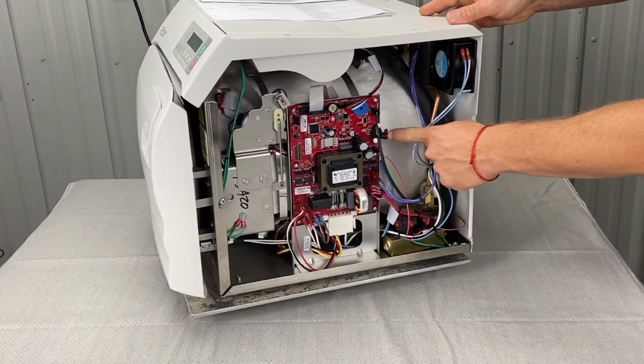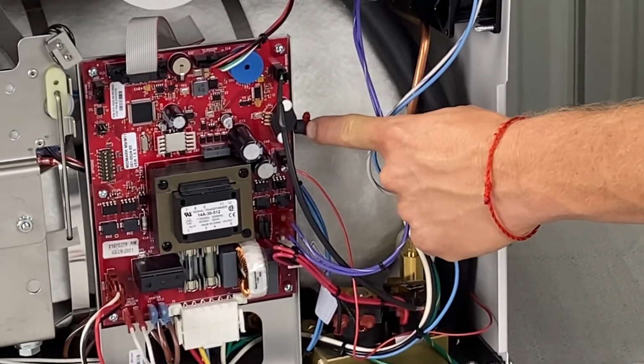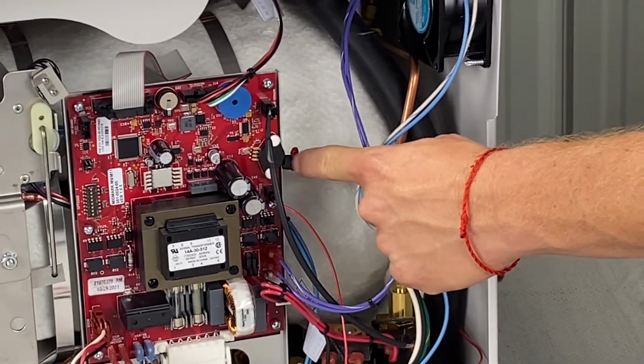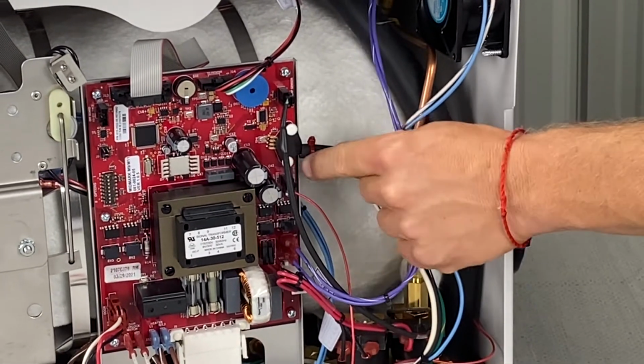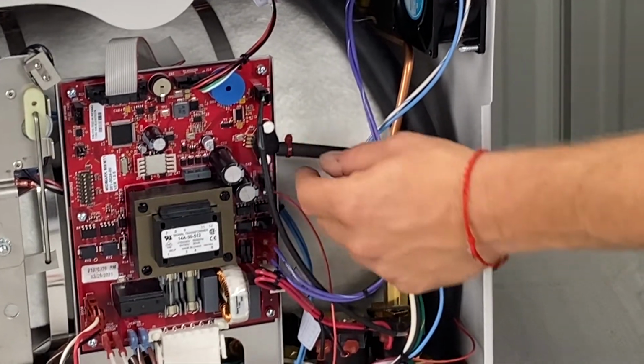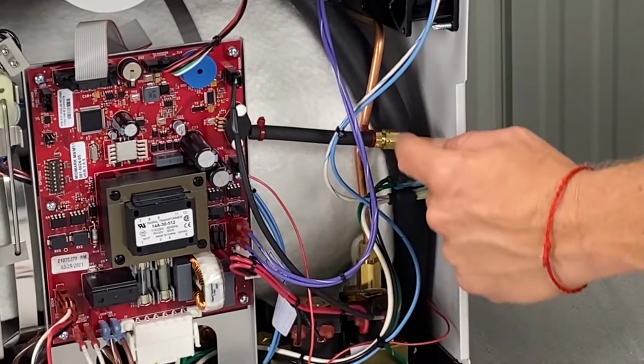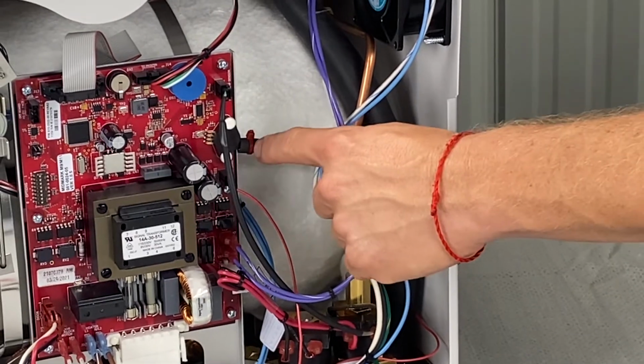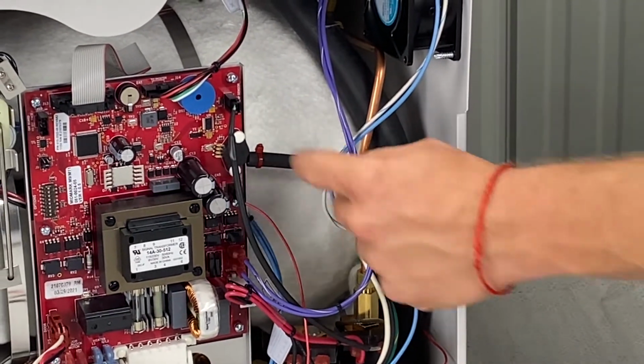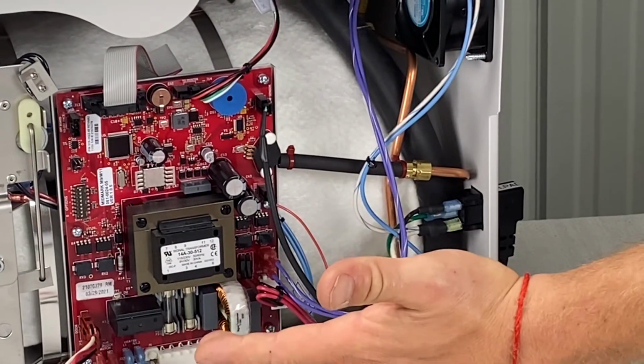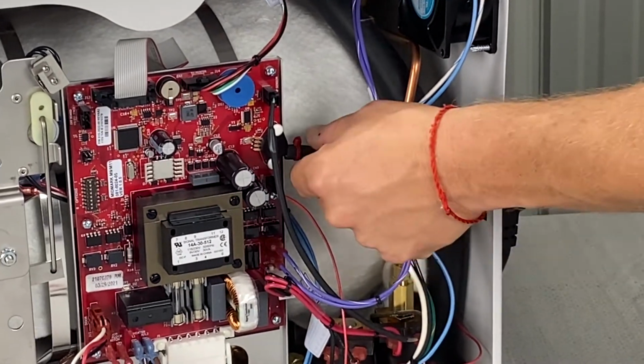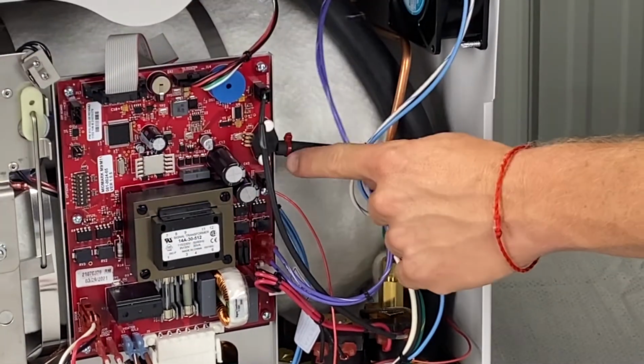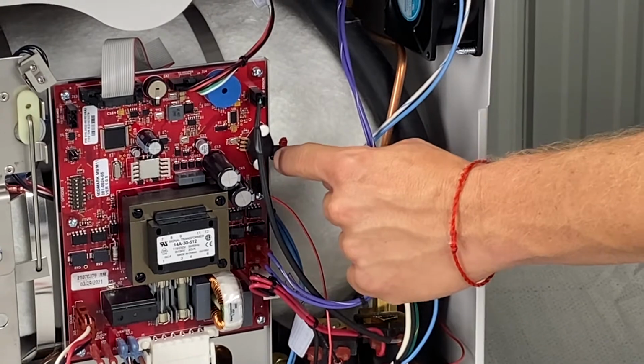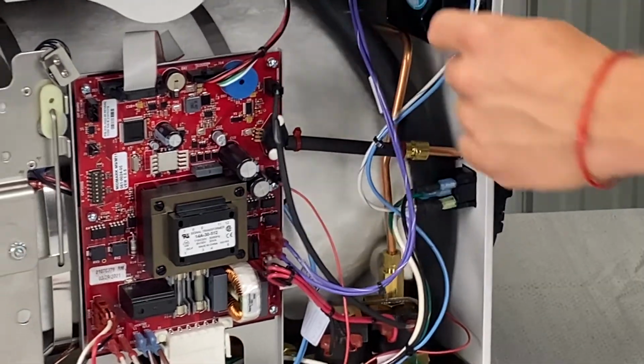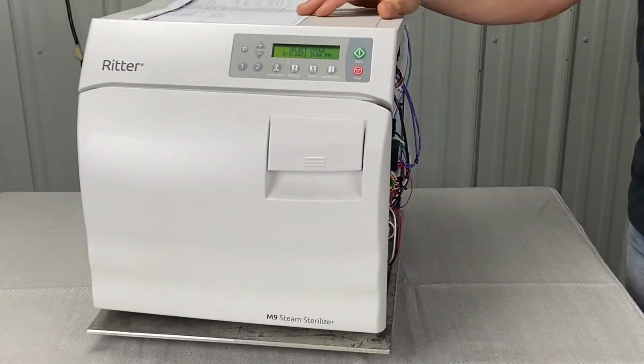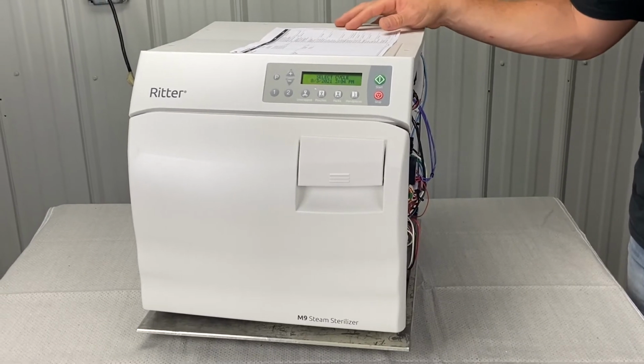Okay, so there's zip ties here. That's all that hold these on. Sometimes these will kink it and it'll spray out, or they become loose or they slide back too far. If you have an older unit, you might want to pull that off completely. Obviously not when it's under power, but pull it off, because once you pull this off, pressure will fly out. You pull it off, you recut these rubber pieces to get a nice fresh tight squeeze on the nipple there.